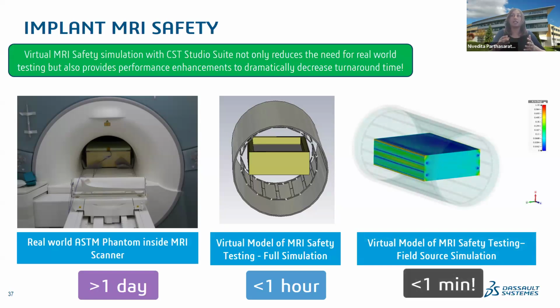We're starting with a real-world ASTM Phantom. When we're talking about a biophantom, it's essentially just a cylindrical vessel that is filled with what we call a tissue simulating liquid. That is a liquid that mimics the dielectric properties of human tissue under specific frequency and testing conditions. And it's a very common test standard that is accepted by the FDA in order to look at safety and compliance. So on the left here, you're looking at a real-world ASTM Phantom inside of an MRI scanner. You can imagine in order to build this Phantom, obtain the tissue simulating liquid, place it and do all of the tests and measurements, it would take roughly up to a day.